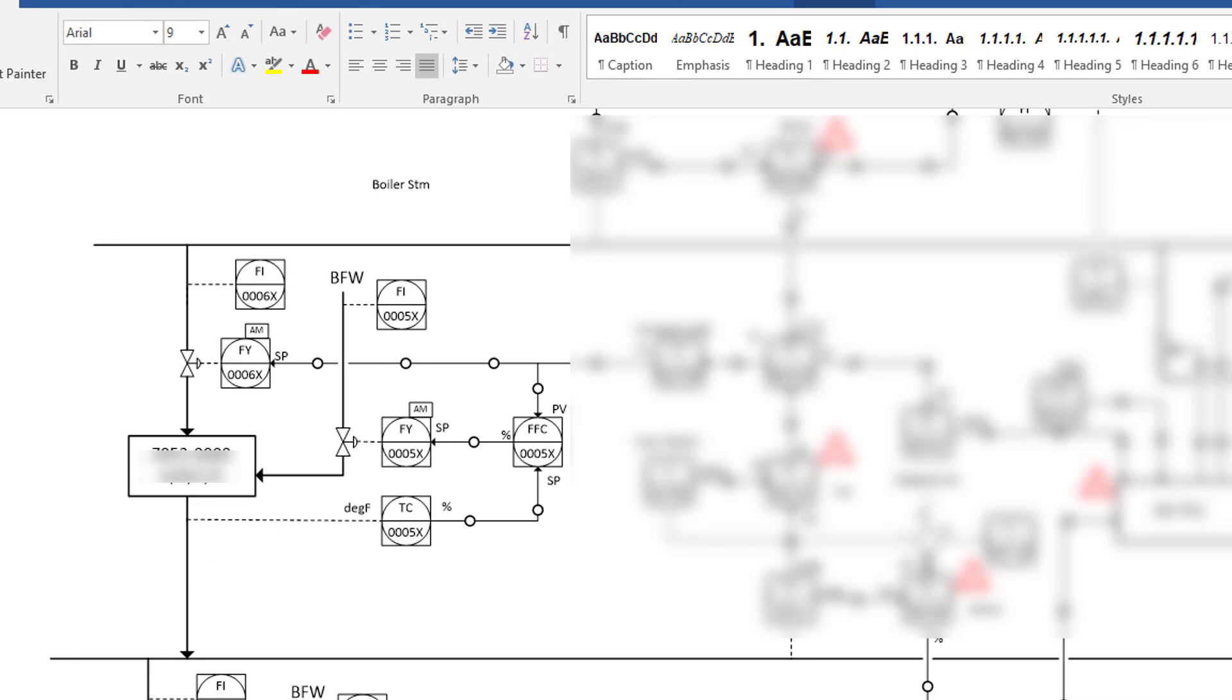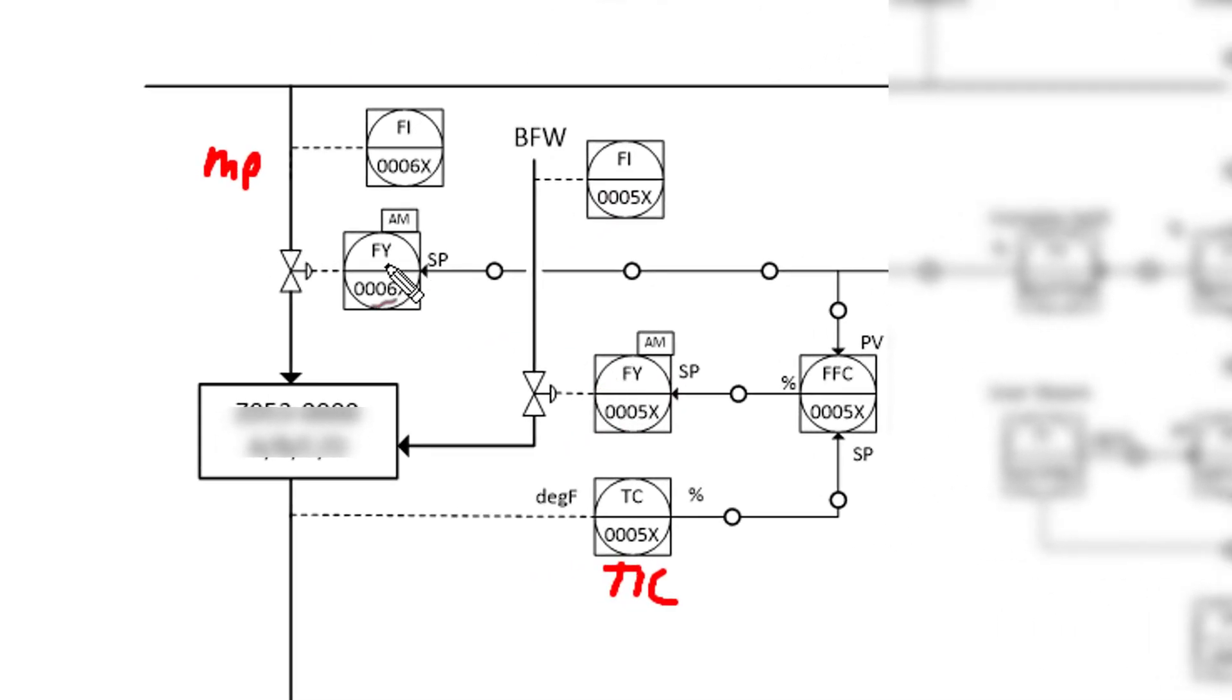I'm going to have to blur out a few of these numbers, but here is the temperature controller. Let's assume that's your master TIC. Here's your steam, that's your MP steam—well in this case it's HP steam—here's your boiler feed water. We're not really using these flow measurements. What we do is we take the output of this valve—it's drawn quite badly unfortunately here. Take the output of this valve, so the valve positioner signal as percent.